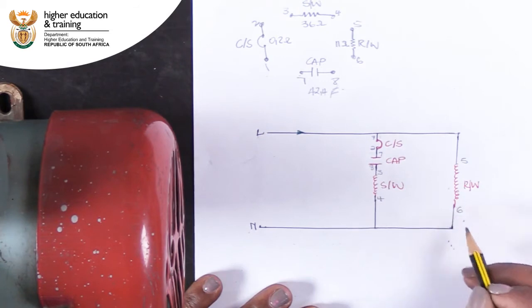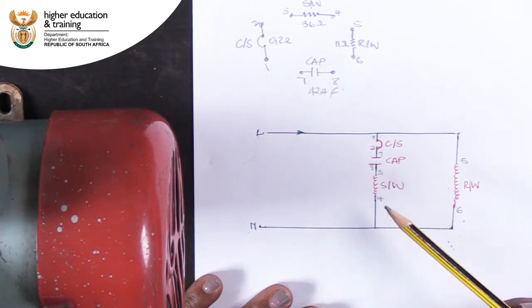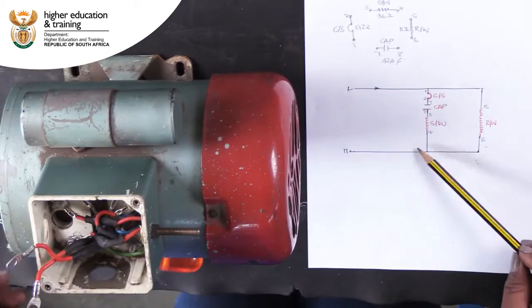Now we can see that to correctly wire the capacitor into the motor, we need to connect it between the centrifugal switch and the start winding. In other words, between points 2 and 3. Therefore, points 2 and 7, and points 8 and 3 must be connected.